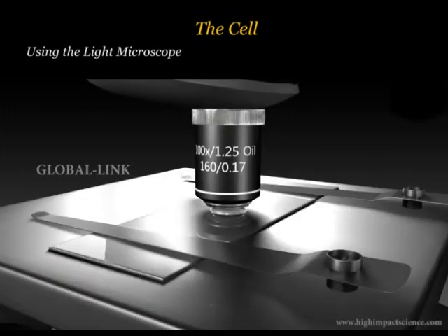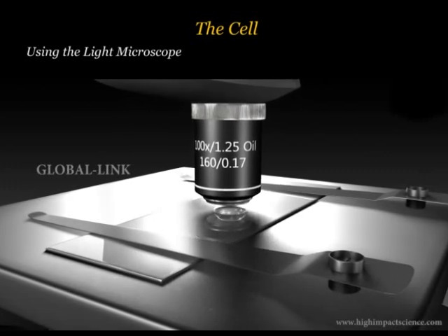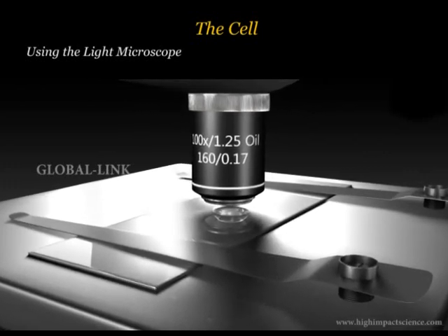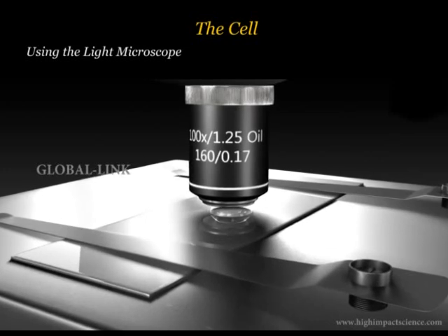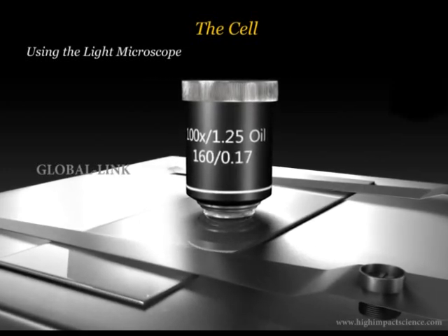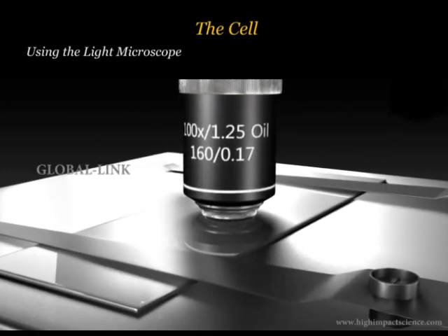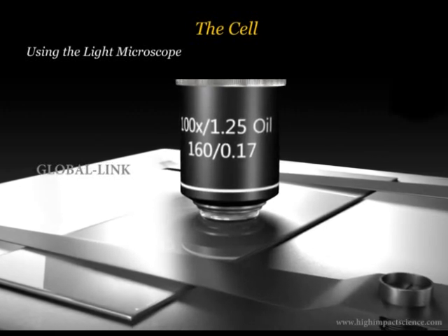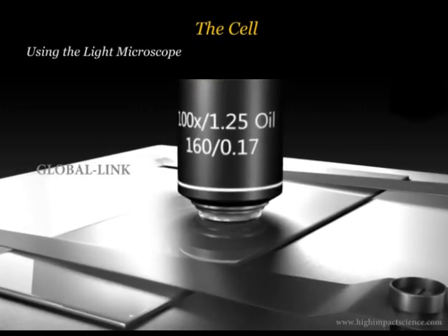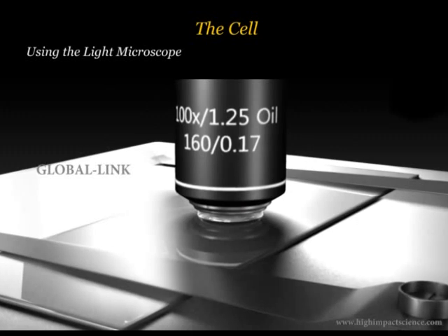Some microscopes have a special type of lens called the oil immersion lens, 100 times. This lens is used by placing a drop of oil on the top of the cover slip and adjusting the position of the objective until it touches the oil. The oil bends light more than air so that more light can enter the microscope.